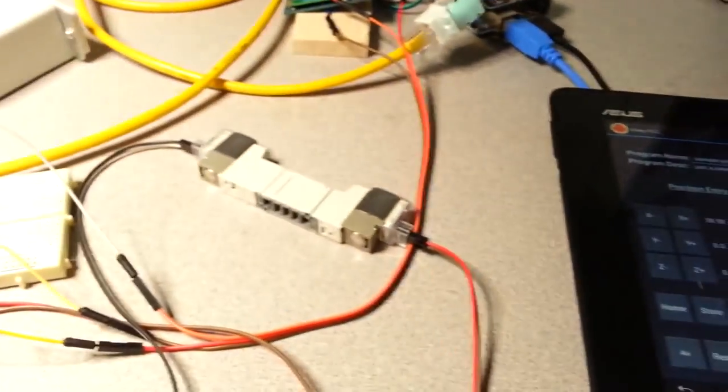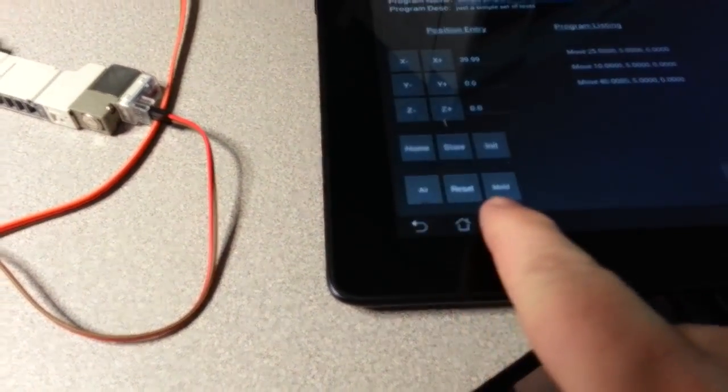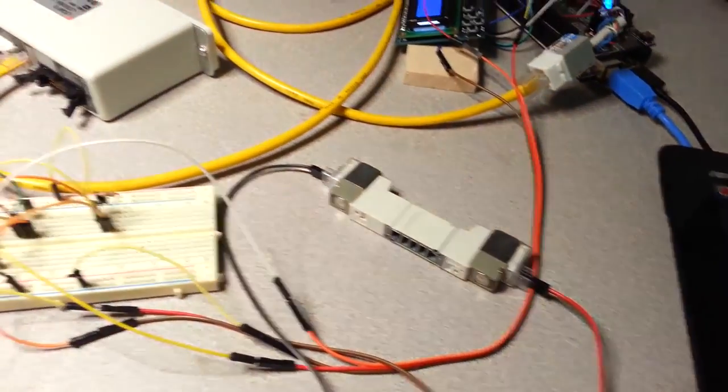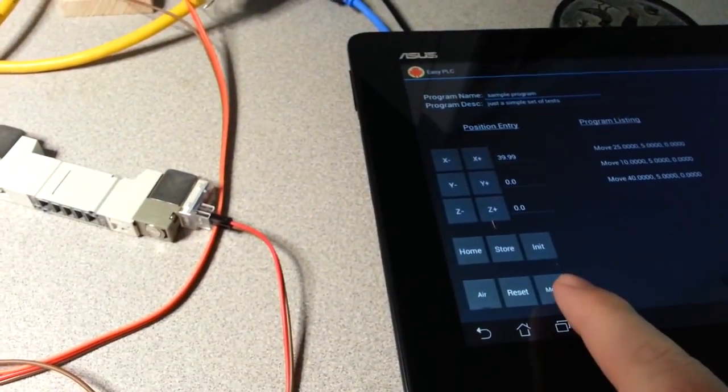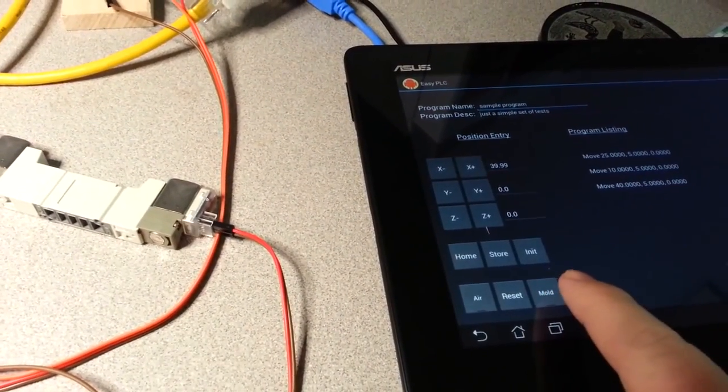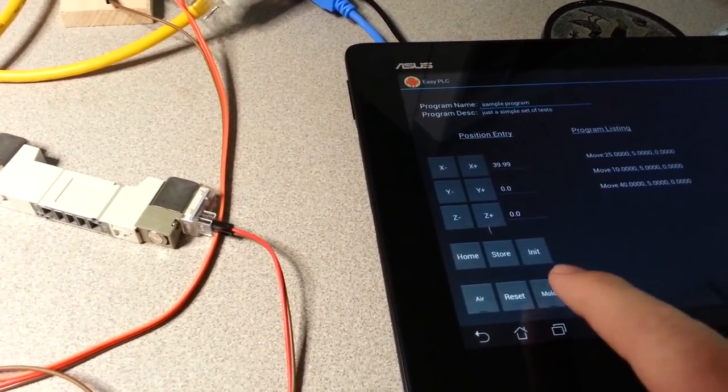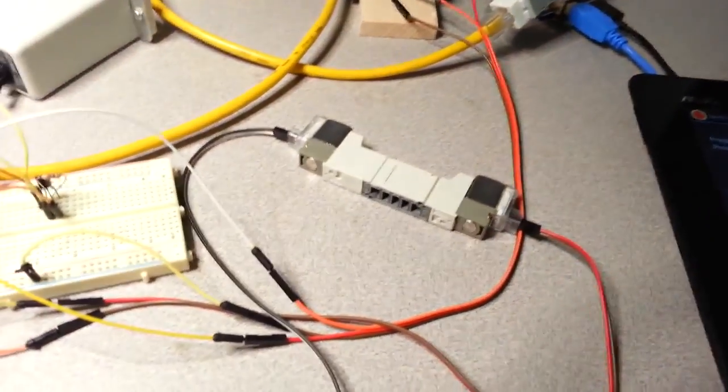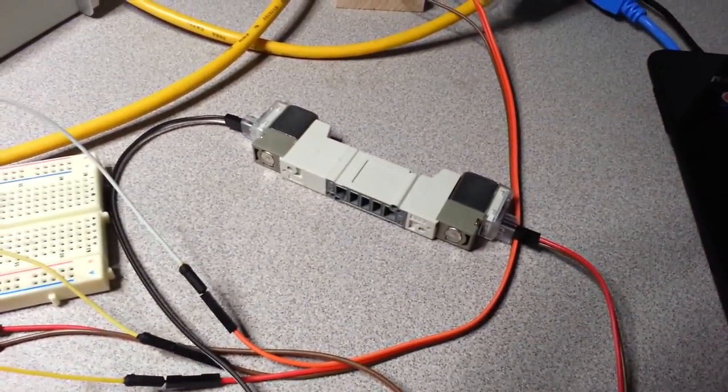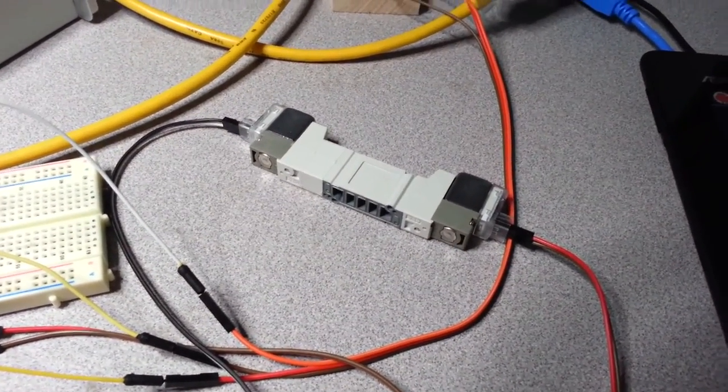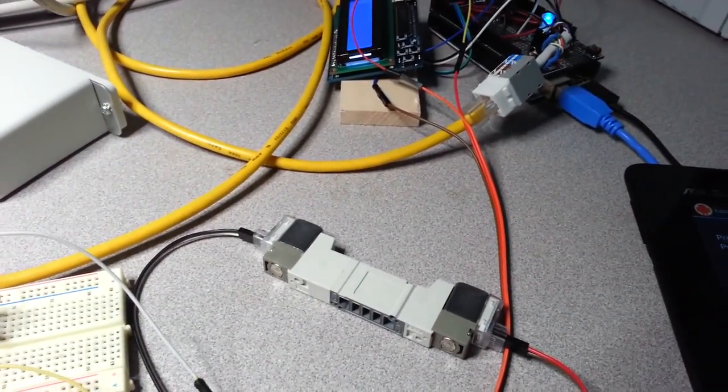Similarly, the air relay and the mold relay are the things that trigger. Now, right now it's assuming the mold is in the retracted position. If I say, okay, I want to move it forward, when I press this button it's going to trigger one of these relays and then wait for a certain amount of time for the endpoint—the end stop—to get triggered.